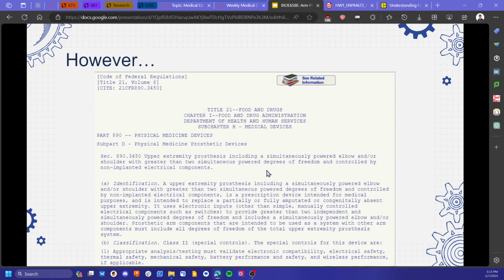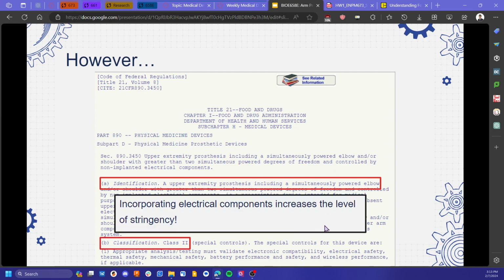So there is a caveat though. There are more complex prosthetics that have motors and electrodes, and that's an electrical component, and that kind of makes it more into electronic, as well as a mechanical device, right? So now there's an increased stringency of regulation. So now the classification is bumped up to Class 2, and now is no longer exempt. As you can remember in the previous slide, it could be exempted even as Class 2, but this Class 2 is not exempt, and requires special controls on top of the general controls. Basically more stringent when you incorporate motors and electricity into the device.